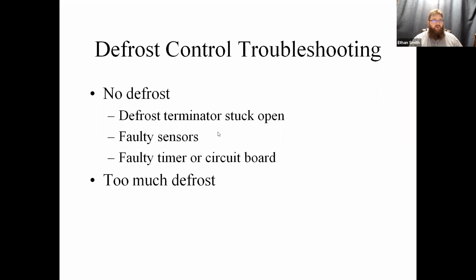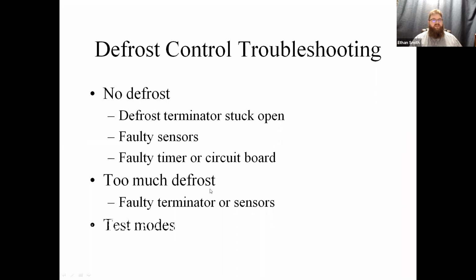Okay. Other cases would be if it's defrosting too frequently. This can show up as a capacity problem where the heat pump's not able to keep up or you're running excessive electric heat. So this could be, again, faulty sensors or timers. So you can use the test modes on these things to determine a lot of this.